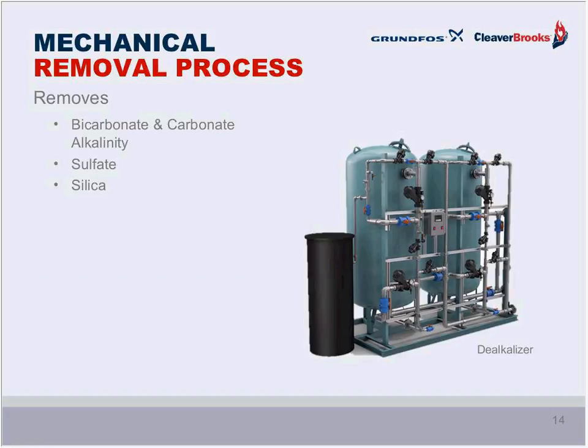Now, these can largely be mitigated by using a dealkalizer. Looking similar to a water softener in its appearance, this mechanical removal system uses an anion exchange of salts rather than a cation exchange as is used in the water softener. Now, it's a technical difference, with the same result in removing much of these impurities from the boiler's feed water.